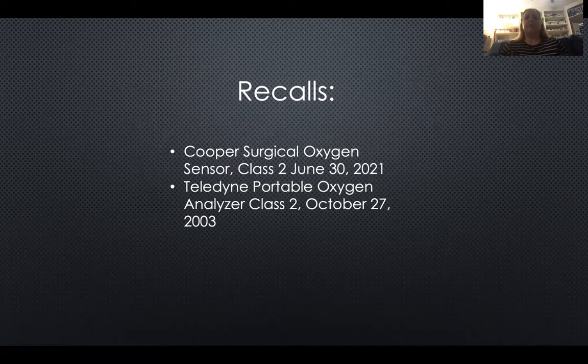Recalls. Two recalls I found were the Cooper Surgical oxygen sensor and the Teledyne portable oxygen analyzer. The Cooper one had an issue where you'd set an oxygen level and an external analyzer was reading 3 to 12% above or below what it should be, and it would not alarm, so they pulled that one. And then the Teledyne one is supposed to have a light that lights up when your batteries are low, and that wasn't working, so they had to pull that one.